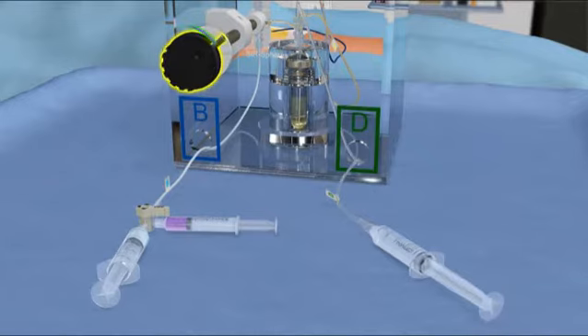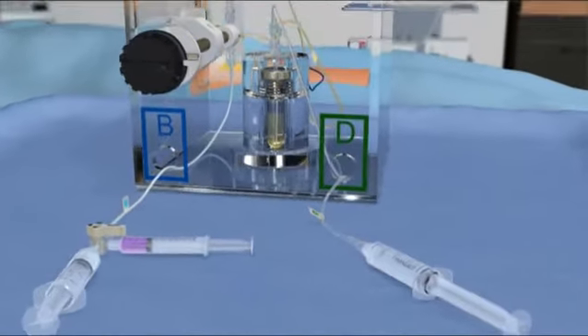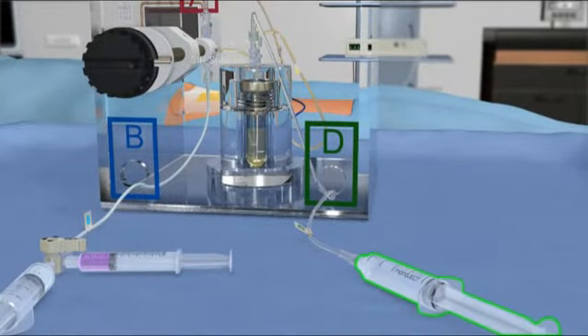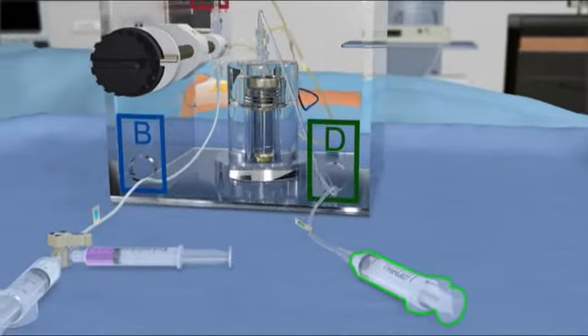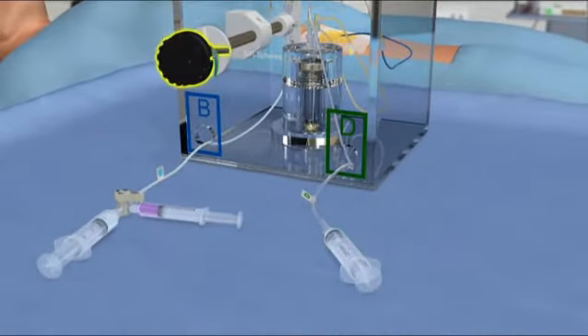Turn the stopcock control knob until it is in the on to the microspheres position, and gently infuse the air into the V-vial. Watch the air bubbles in the V-vial. The air will force the residual suspension out through the C needle sitting on the bottom of the V-vial. Turn the stopcock control knob off to microspheres before air starts entering the A-line to the patient. With the stopcock control knob in the flush contrast position, flush the A-line with water for injection. This will clear the catheter of any remaining microspheres prior to removal.